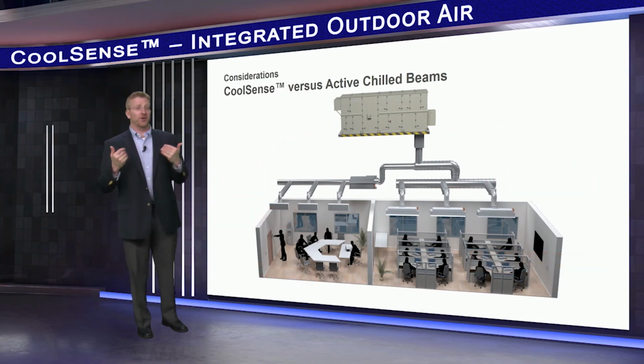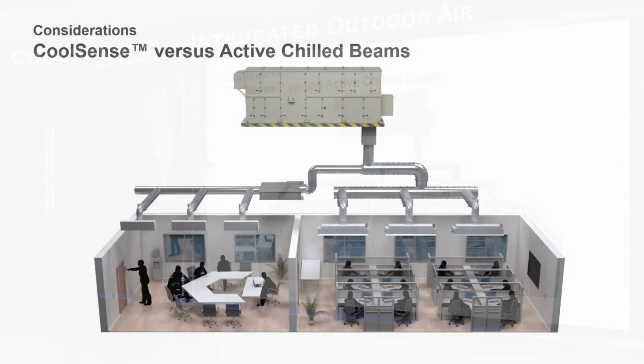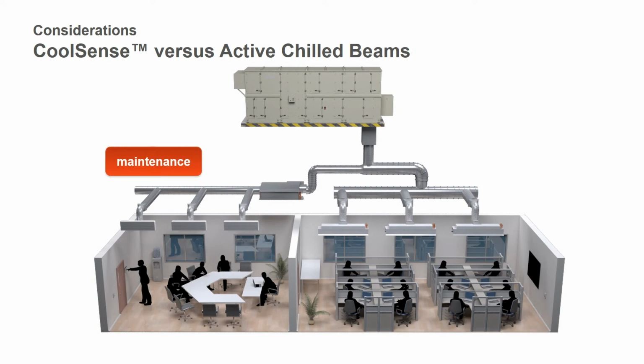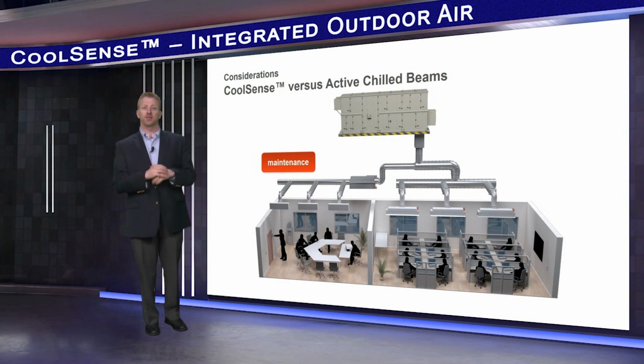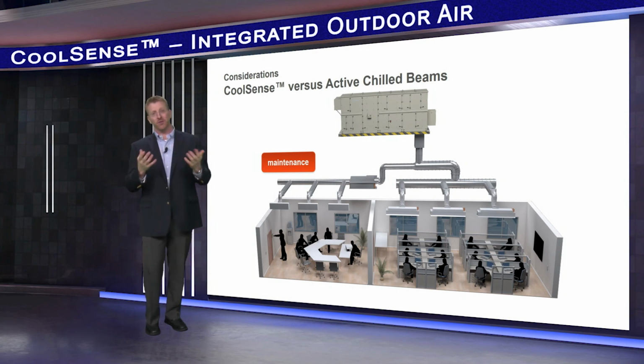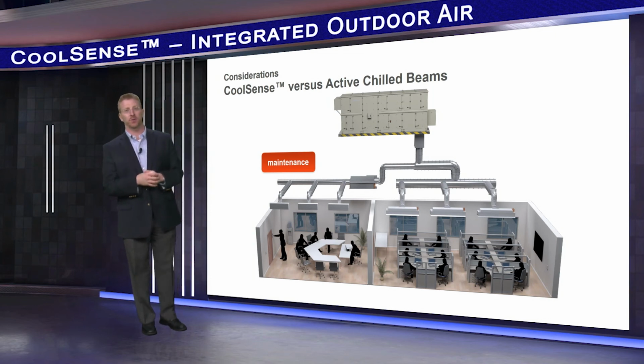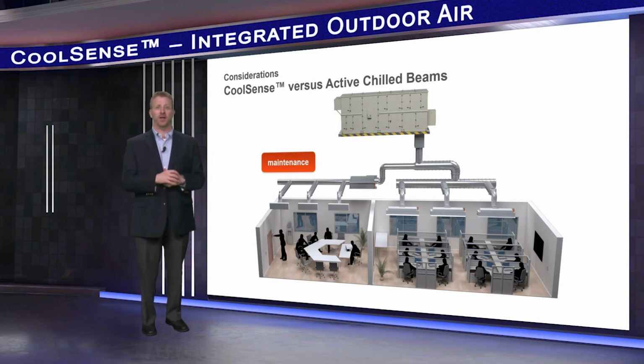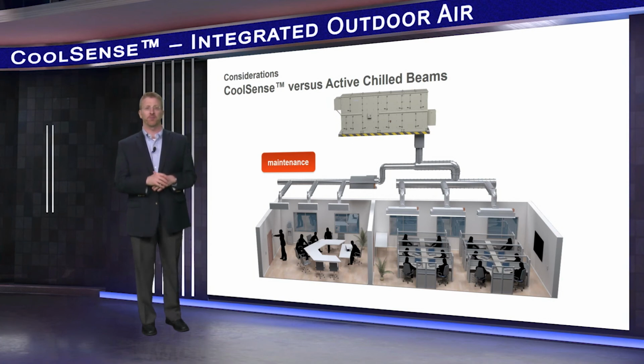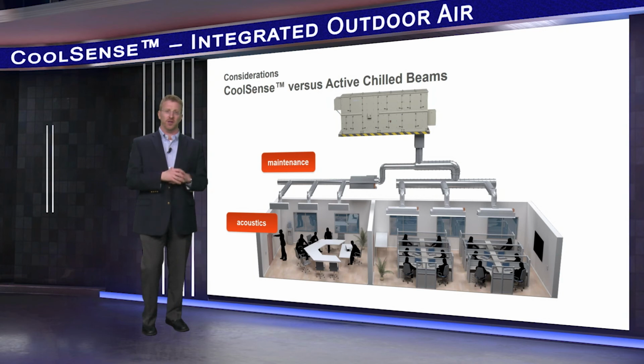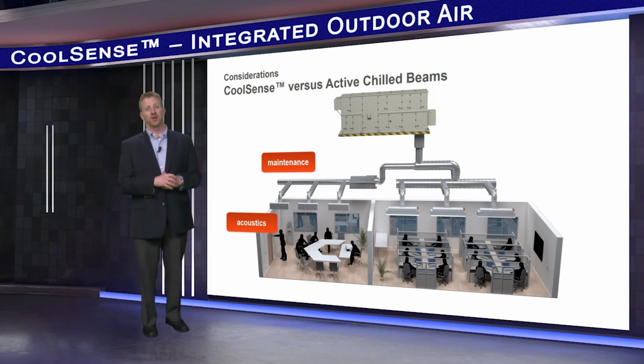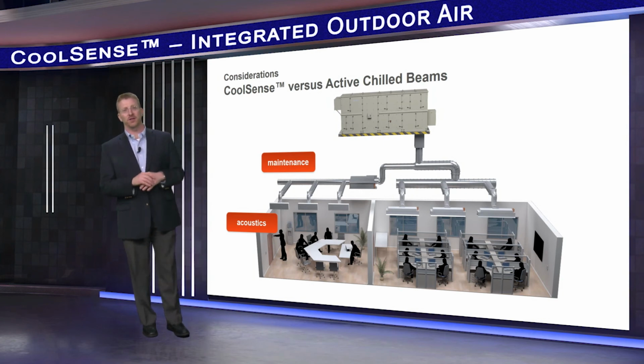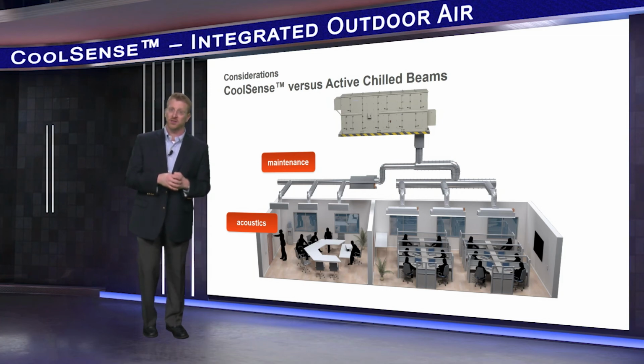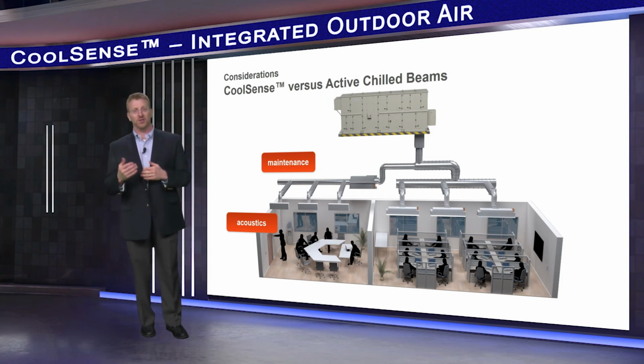So what are the potential considerations when using CoolSense rather than an active chill beam system? Well, there is a possibility for more maintenance to be performed in or near occupied spaces. If, for example, you want to use a filter to clean the recirculated air and improve IAQ, the filter would need periodic inspection and or replacement. Other than this, there's no other planned maintenance required after commissioning. Since each terminal unit is equipped with a fan located near the occupied space, there is also potential for higher sound levels. Obtaining a manufacturer's sound data that is tested and measured in accordance with AHRI's Standard 880 can help predict sound levels in the space.